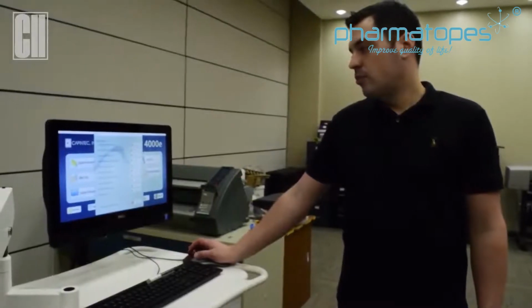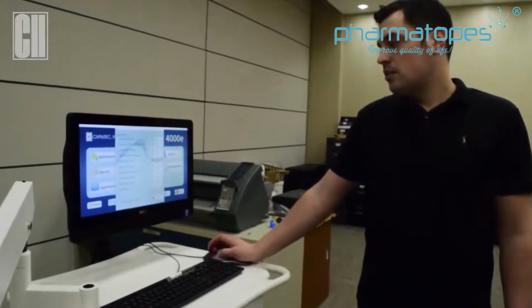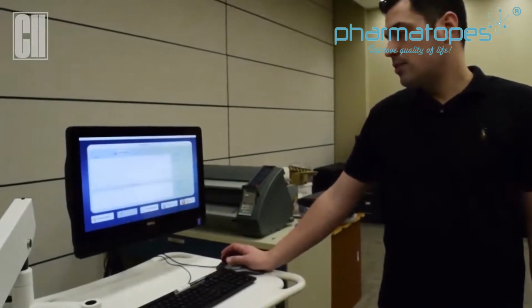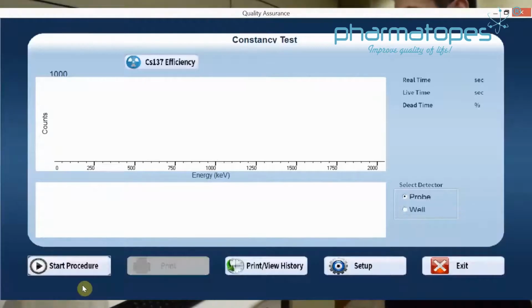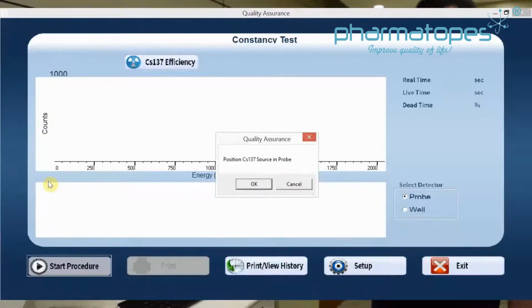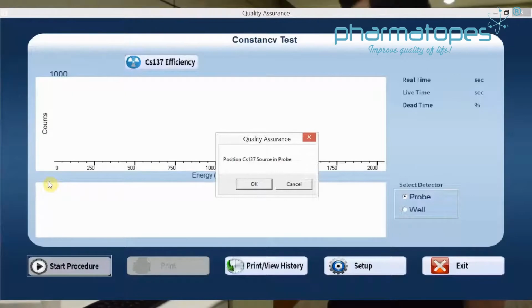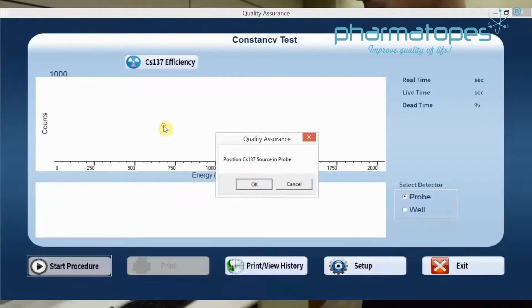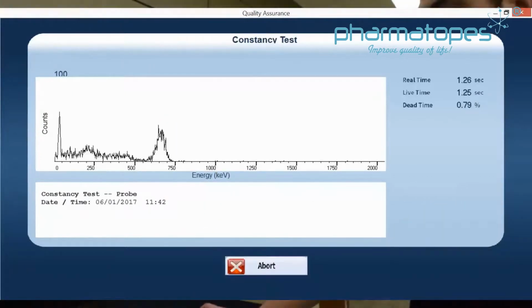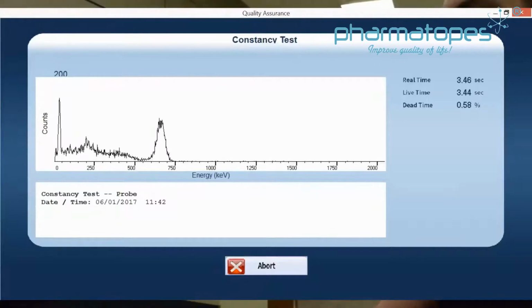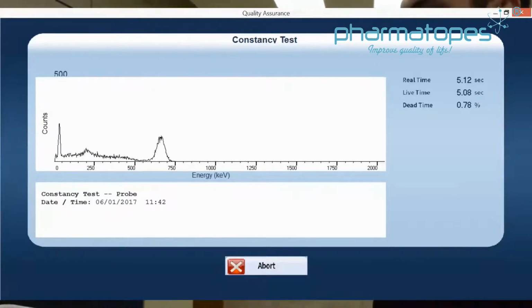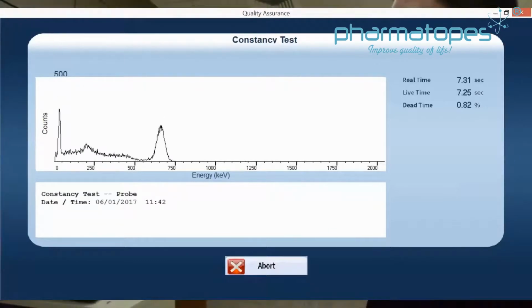That would be to perform the constancy test. So we'll go to that location, and now we do select the detector you'd like to check, and then do start procedure. And it's telling us to position cesium in the probe, which is already in there at this point. We're going to click on OK, and we want our deviation to be plus or minus 5% for a successful constancy check.